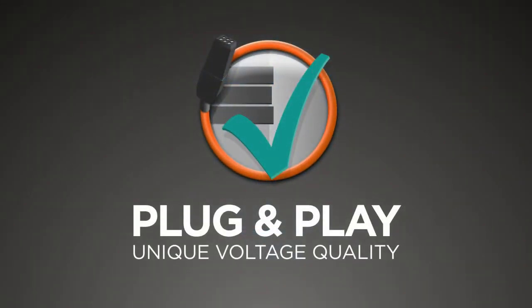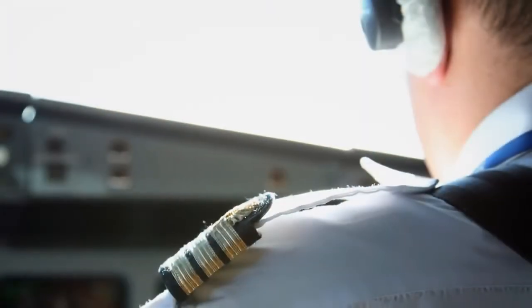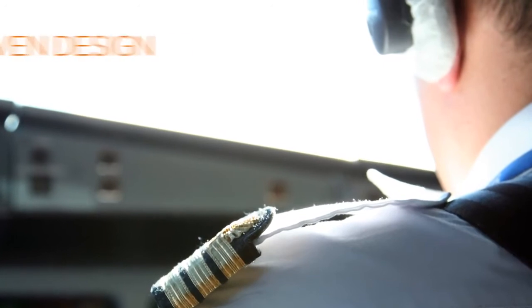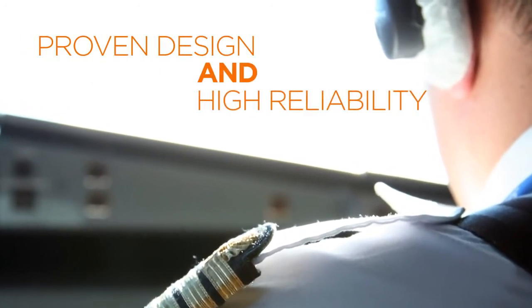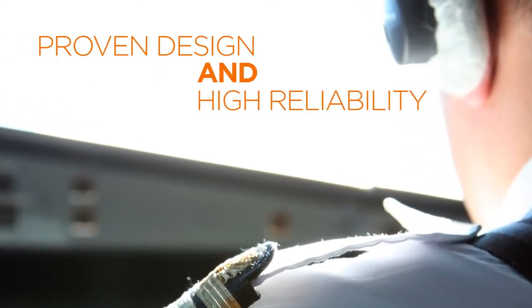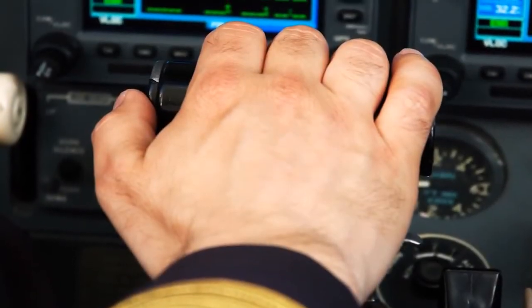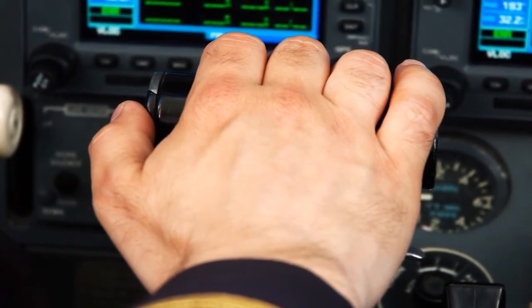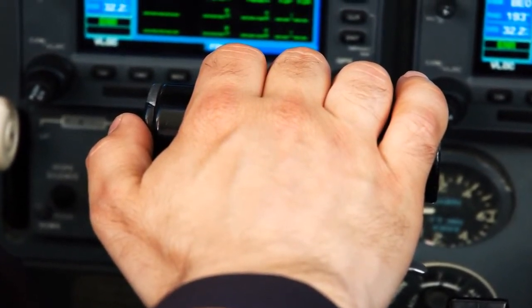Modern aircraft are fitted with more and more electronic equipment. These expensive systems are extremely sensitive. For the captain to shut down the APU and transfer to ground power, and for the airline and airport operator to be sure this won't give problems, the voltage of the aircraft plug must be both steady and completely predictable. Current voltage requirements are 115 plus or minus 3 volts, regardless of load conditions.